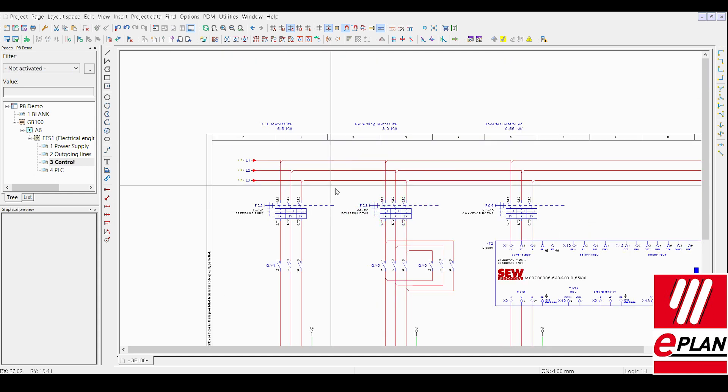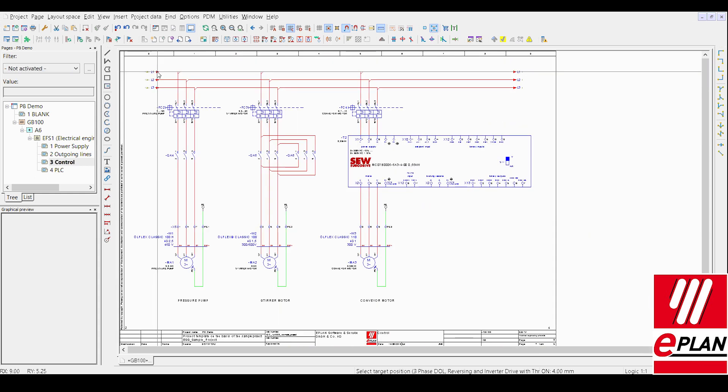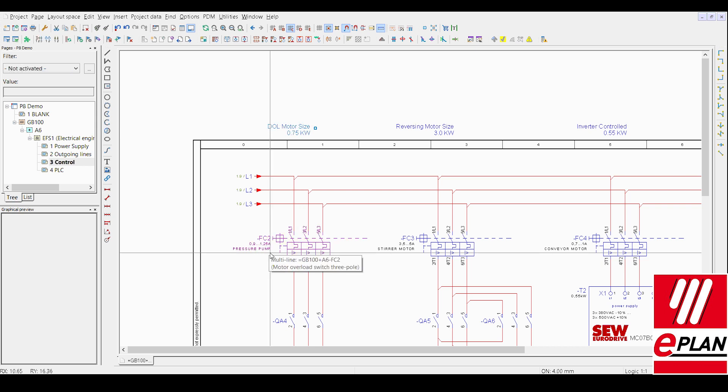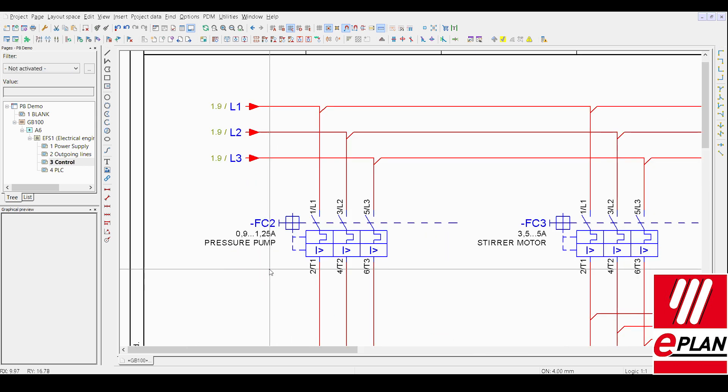If for instance the specification has changed what we can do we can approach the data table up here and we can choose a new value set. So now what we'll do we'll go with a slightly smaller range, 0.75 and now the 7 to 10 amp will change to 0.9 amp.